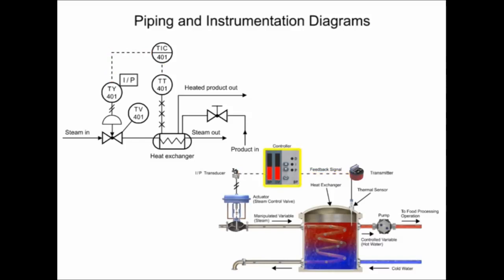The controller and indicator is the instrument where the transmitter sends an electrical signal and is shown in the functional identifier as the second and third letters I and C. Balloons with a solid dividing line indicate that the instrument is board mounted.